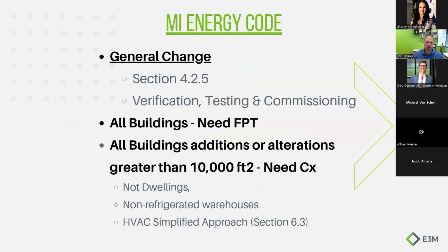Functional performance testing is required for all buildings, all projects, regardless of size. We're going to dive into some requirements of individual systems, but functional performance testing is a scaled-back version of full-on commissioning. It removes some early design-phase requirements and some site inspection requirements, but it ultimately focuses on whether the system operates and functions the way it's supposed to when the project is completed.